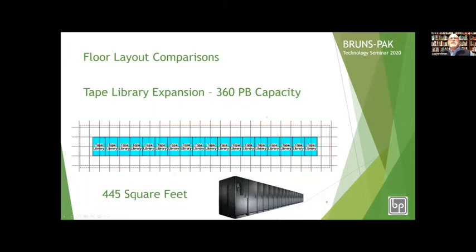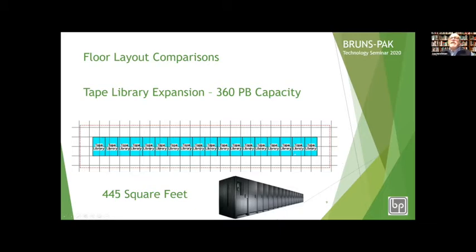Next I maxed out the comparison. Certainly 360 petabytes is not a typical data center storage amount, but this shows the extreme. The same tape library maxes out at 18 frames — two robots running up and down moving tapes — taking up 445 square feet. This solution requires a floor level to within half an inch over the run of the tape library. The reason 360 petabytes is used for the next two analyses is because that's the max this library does — it's roughly 20 petabytes per frame.